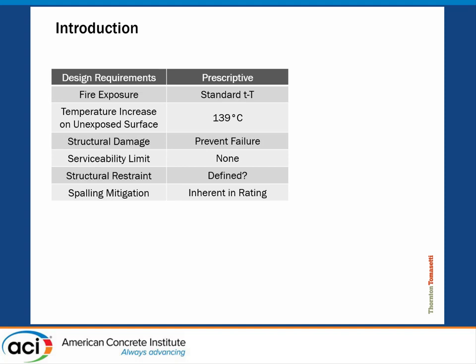What does failure mean? It's not well-defined. Complete loss of load-carrying capacity would be failure, but there could also be a serviceability limit — you could fail because you deflected six inches, and that may be a failure for that particular building or situation. There are no serviceability limits defined whatsoever. Structural restraints are defined, but it's a big question mark — restrained or unrestrained — and there's an inherent restraint on end boundary conditions for all fire resistance ratings that can cause problems if not properly defined.